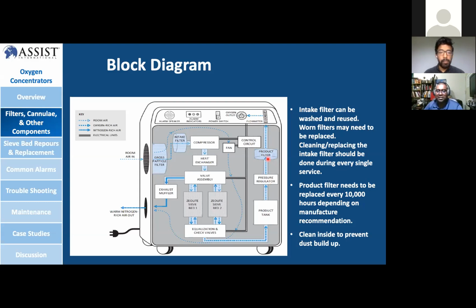So always make sure that you clean inside to prevent dust buildup. When you have so much dust inside the oxygen concentrator, your fan is not going to work properly, and eventually you're going to create heat inside. Remember that in an oxygen concentrator, there are always two thermal switches. One is for inside the system, another one is inside the compressor. So when your fan doesn't work properly and your filter is full with dust, you don't get proper room air going in, and all this is going to create heat inside. Eventually either the room thermal switch is going to trigger, or the compressor thermal switch can trigger, and eventually it fails. So make sure you keep it clean, make sure the filters are working properly, and replace the filter during the service.